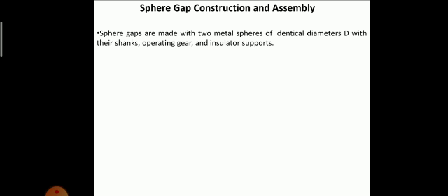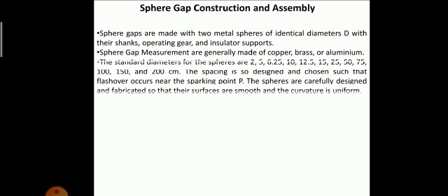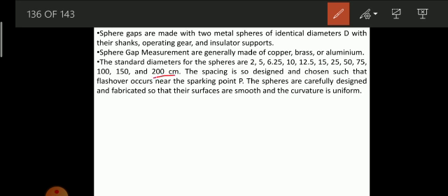Now here some basic configurations are given. Sphere gaps are made with two metal spheres of identical diameters d, with their shanks, operating gear and insulator supports. Sphere gap spheres are generally made of copper, brass or aluminium. Generally we go for the latter because it has a low cost. The standard diameters of the sphere are 2, 5, as per BIS standards, going up to 200 centimeters.